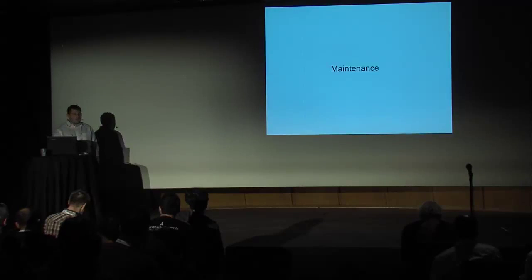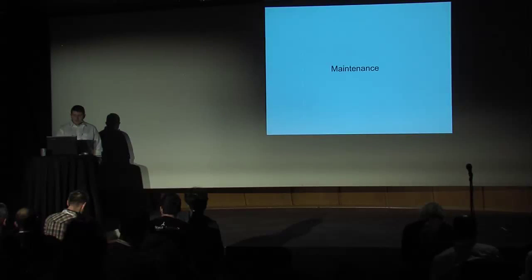So IPMI gives me basic sensors. I can get thermal and CPU type of sensors. If it crashes and burns, I can get a basic log of CPU and DIMM failures. And even those can be iffy. You tend to see hard failures, but IPMI is not the ideal protocol for monitoring servers.